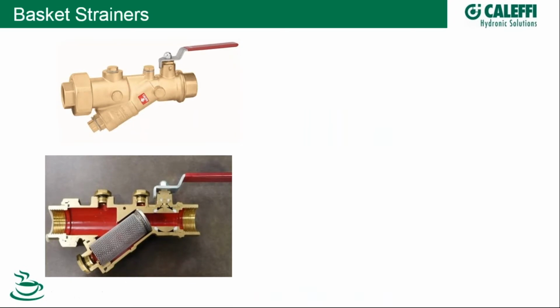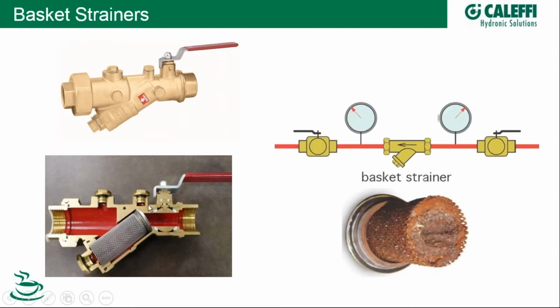The traditional means of getting rid of debris in a hydronic system is basket strainers, otherwise known as Y strainers. So fluid would come into a Y strainer, down into the little cartridge here, or mesh, I should say, and back out to continue on in the circuit. Now, as these do their job and begin filtering out debris, they start plugging up. As they do, pressure drop starts to occur across the mesh or across the Y strainer. As a result, your flow rate is suppressed, even to the point where it's detrimental. So they need to be maintained. When they are clogged up, you'll get more of a pressure drop.